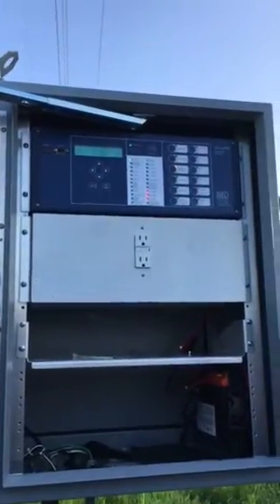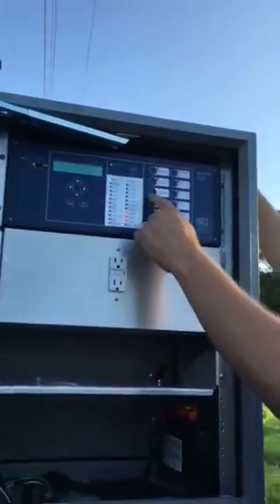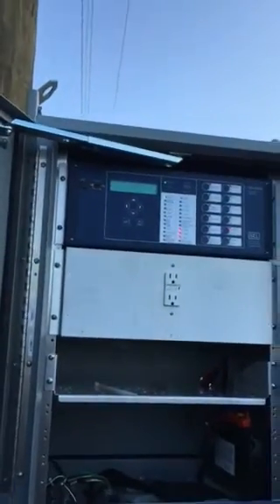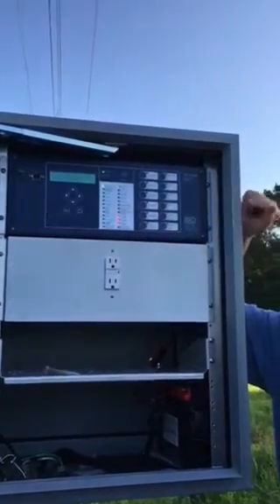If you're out here working on it and you want to take it out where SCADA cannot have control over it, all you have to do is just remote enable it. When the light's on, it's disabled, so SCADA has no control over it. They can't open or close. They see that toggle, but they can't operate.